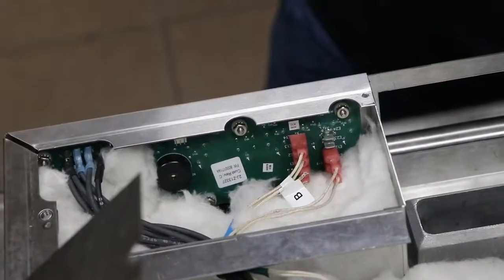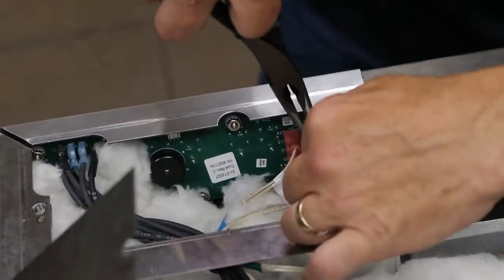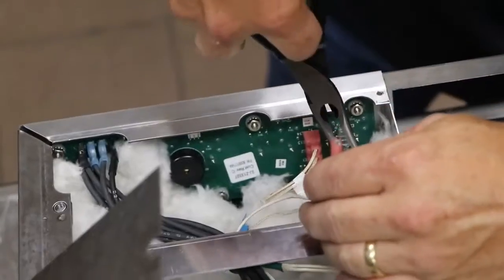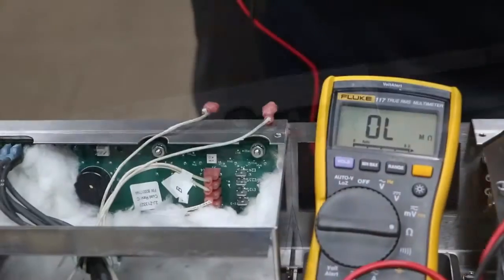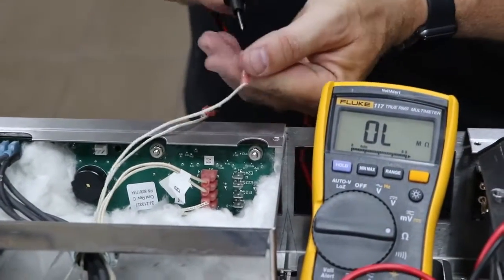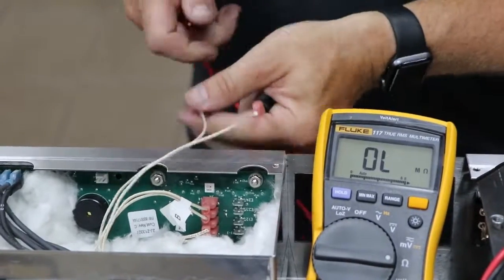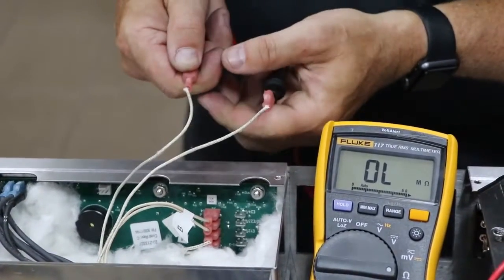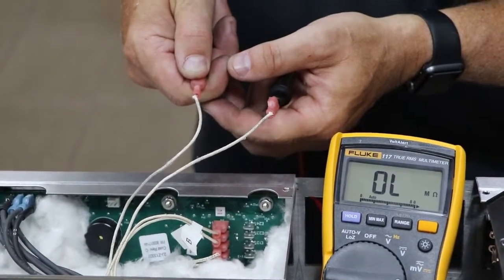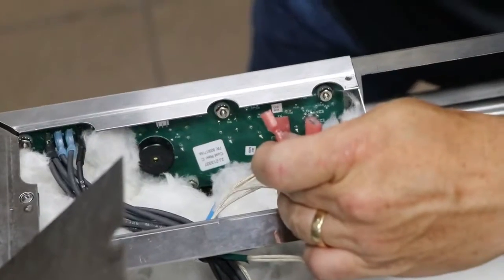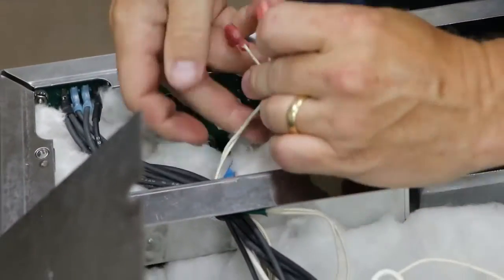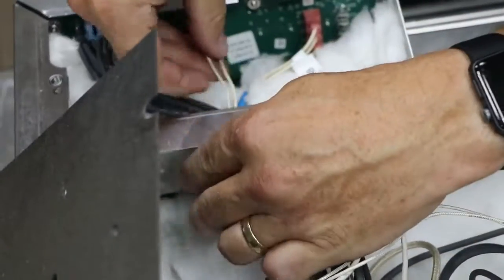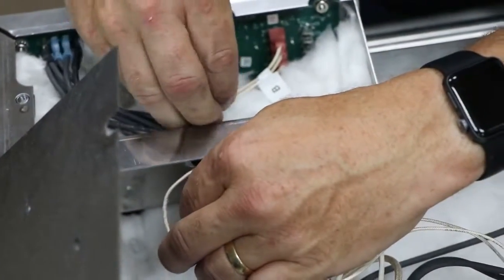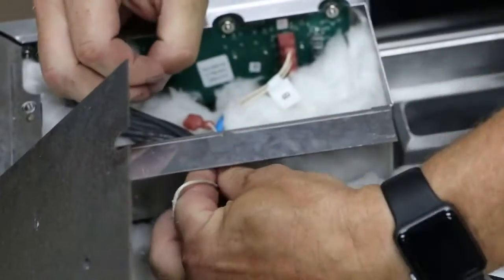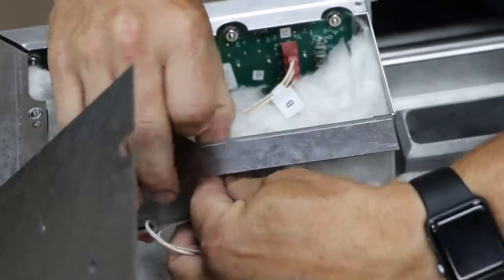Disconnect the probe wires from the control board using needle nose pliers. To check whether the probe is good, check the continuity and confirm it has failed, which essentially reads open on the ohmmeter. Feed the probe wires out of the control heat shield opening one at a time by pushing the terminal through the opening. Do not pull the wires through the opening as you may remove the terminal by accident.